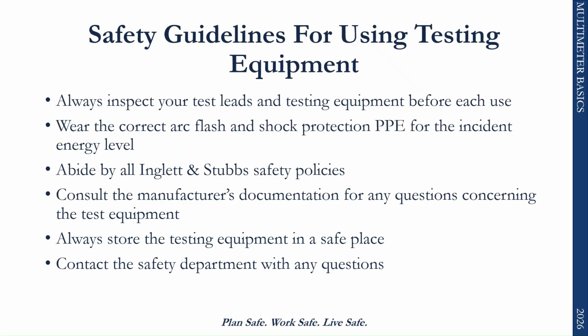To finish up, there are a few safety guidelines that should always be followed when using electrical testing equipment. Always inspect your test leads and equipment before using them. Damaged leads or faulty equipment can result in inaccurate readings or increase the risk of electrical shock. Make sure you're wearing correct arc flash and shock protection PPE for the task and the equipment being tested. Follow company procedures and refer to the manufacturer documentation whenever needed. And if there are any questions about testing equipment or procedures, reach out to the safety department for guidance. Proper testing procedures help ensure that electrical work is performed safely and that hazards are identified before work begins.